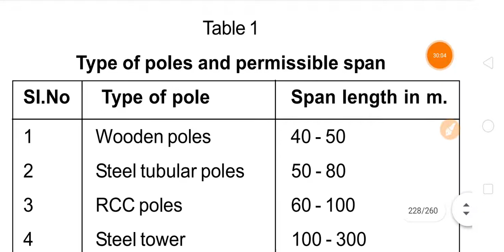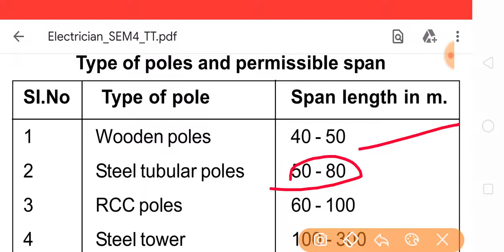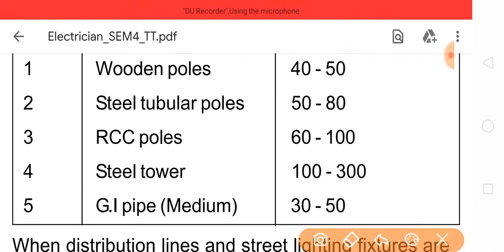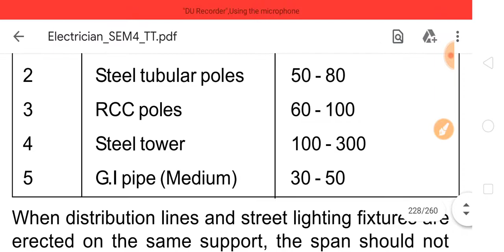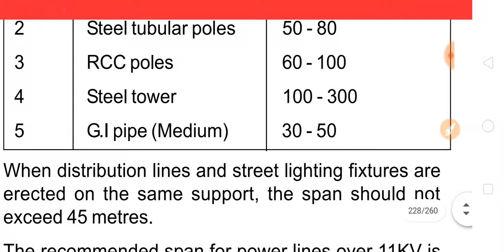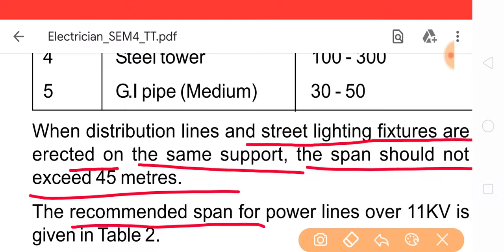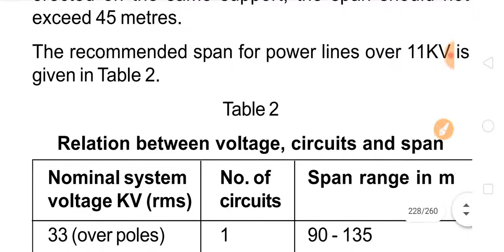Wooden poles: 40 to 50 meters span length. Steel tubular: 50 to 80 meters span length. RCC poles: 60 to 100 meters span length. Steel tower: 100 to 300 meters span length. GI pipe: 30 to 50 meters span length. And when distribution lines and street lighting fixtures are erected on the same support, the span should not exceed 45 meters. The recommended span for power lines over 11 kilovolt is given in table 2.